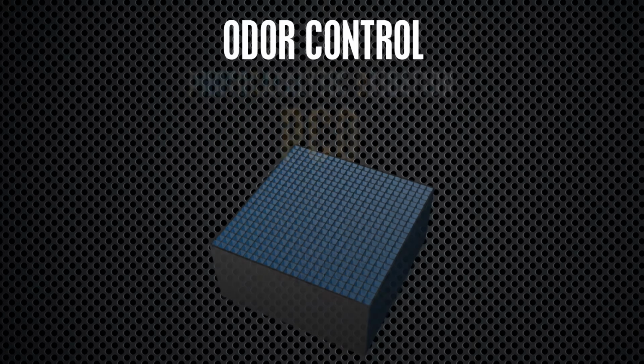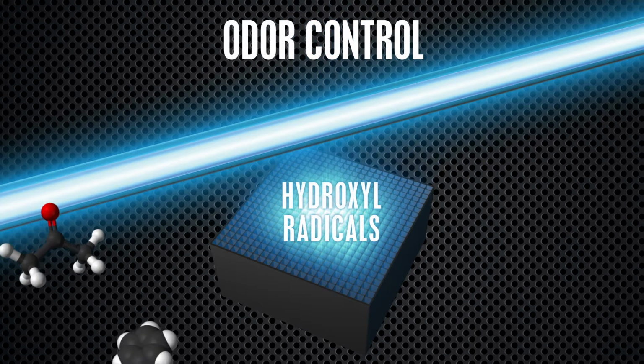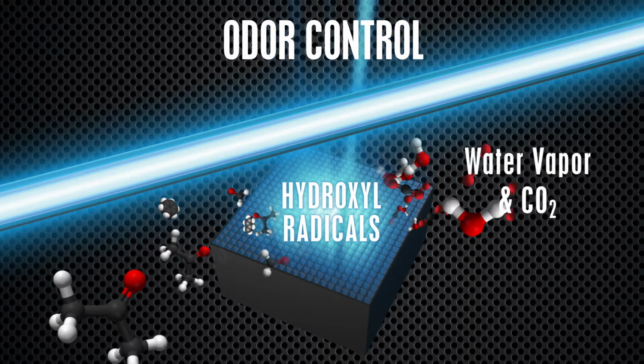APCO technology is based on photocatalytic oxidation, or PCO. This photochemical reaction is created by shining UVC light onto a catalyst, in this case, titanium dioxide. Hydroxyl radicals created by this reaction catalyze VOCs, breaking them down into harmless water vapor and carbon dioxide.